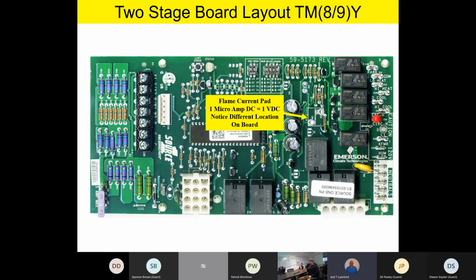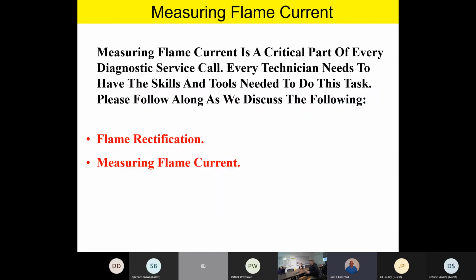Okay, team. Well, let's talk a little bit about testing flame current and measuring flame current. And guys, this is really important. I like to think that every time a technician does a service call, they should probably check flame current just to make sure it's not degrading from the last service call. As a matter of fact, I recommend, when you do your service calls, to mark down on your service ticket what your flame current was.